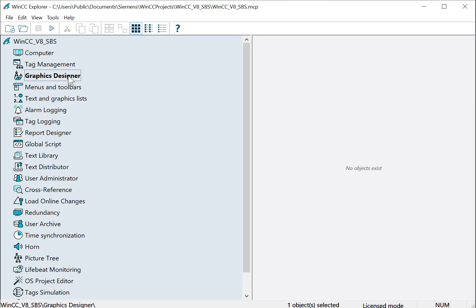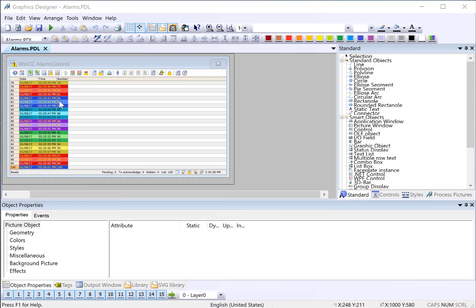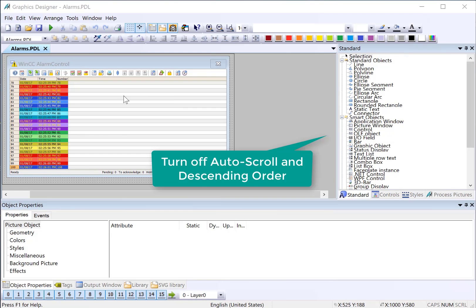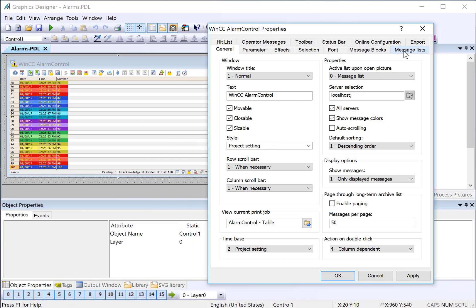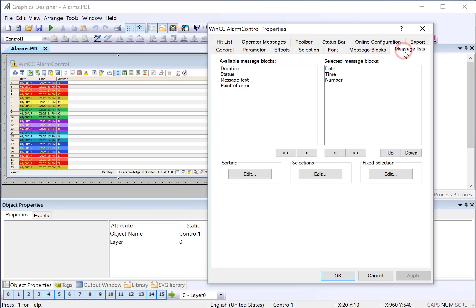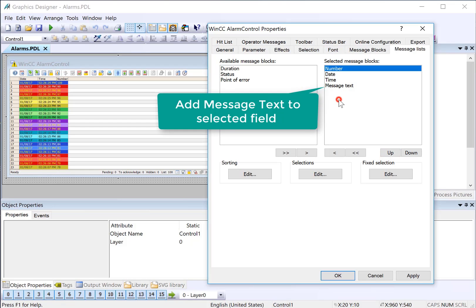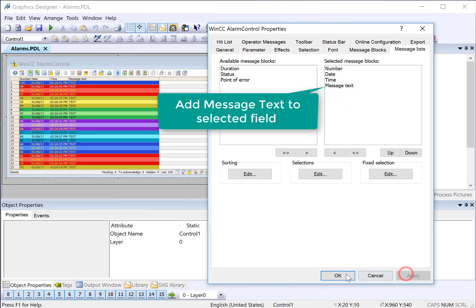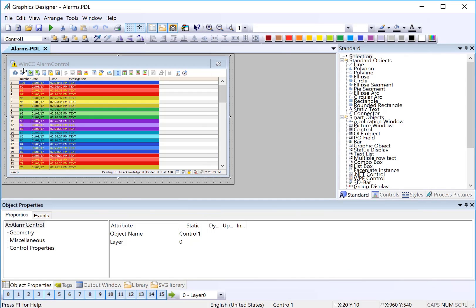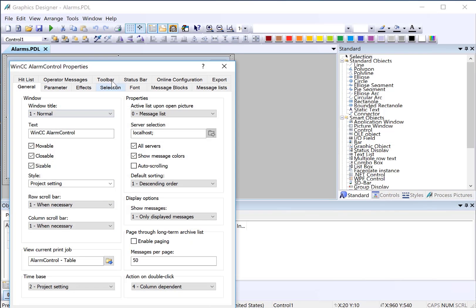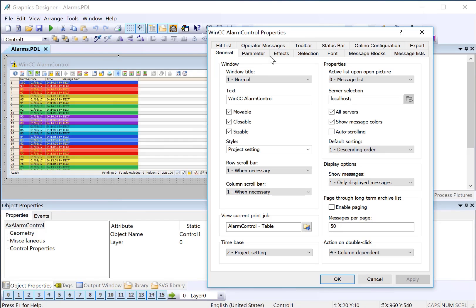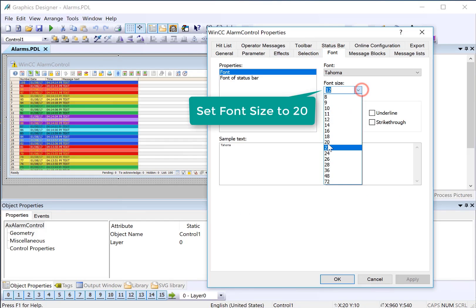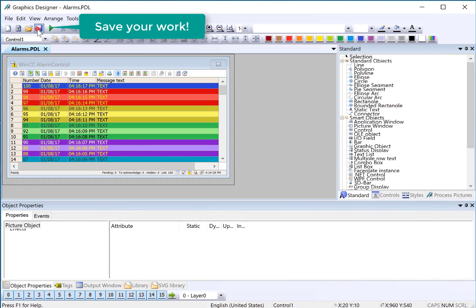Now let's go to our graphics designer, and we'll open our alarm screen. On our alarm screen, we're going to configure our alarm control. I'll double-click, and on the General tab, let's turn off auto-scrolling and set it to descending order. On our message lists, we will add our message text and set our numbers to the first block. And I'll just click Apply and OK. You can see it reformats our alarm control, and it gives us more room on our message text. This is because we set the width to 60. I also want to increase the font size. So I'll go back to Properties, go to Font, and set my font size. That'll make it a little easier to see in runtime. Then we'll save.